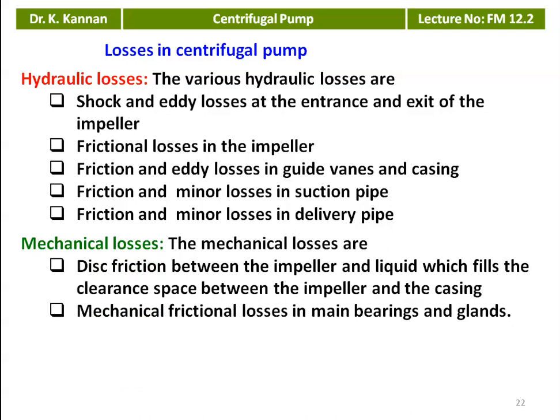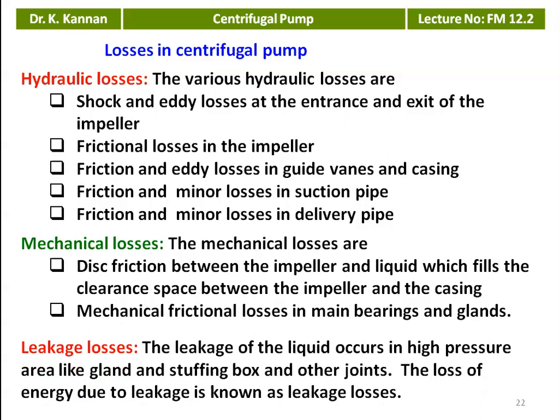The second type of losses are mechanical losses. These include disc friction between the impeller and the liquid which fills the clearance space between the impeller and the casing, and mechanical frictional losses in the main bearing and the gland. At the end of the shaft, we have the main bearing, general bearing, and a gland stuffing box. There are also leakage losses — loss of energy due to leakage at high pressure areas like the gland, stuffing box, and other joints.